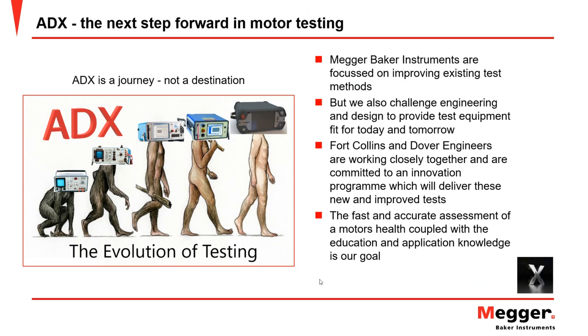Now, if you can imagine the turns having that high current and voltage rushing through those turns, electricity always wants to find its shortest path. So if there's weak insulation between some of those turns, it's going to try and jump over those turns and skip them. As soon as they skip them, that's basically a short, and those turns will heat up and start to damage the motor. So the insulation between the turns is the weakest, and the one that conventional equipment won't be able to test for.